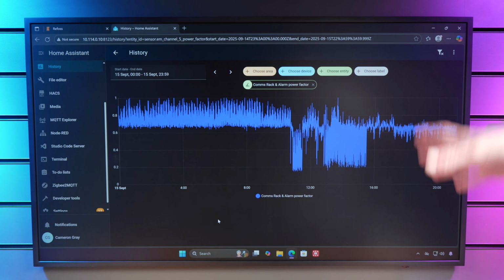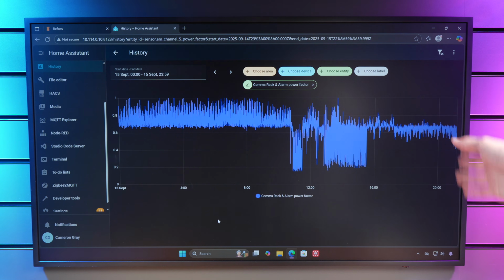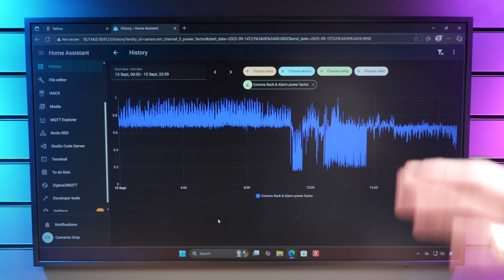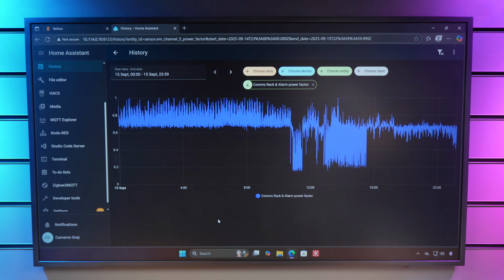So what we're looking at here right now is the power factor across the entire day for my comms rack circuit. This feeds my rack, which is a very constant load, and I've tested it with a plug-in power meter, and the power factor of that sits pretty consistently around about 0.7. Maybe down to 0.65, maybe up to 0.75, but it's very close to around about 0.7.